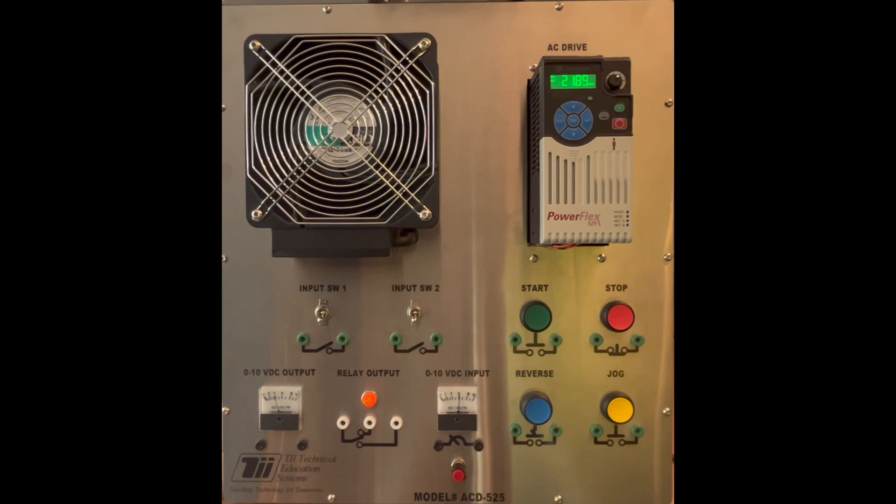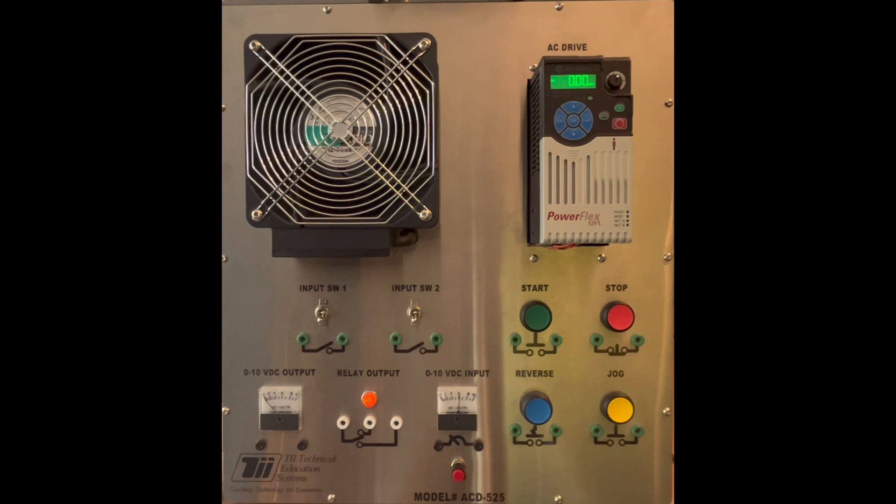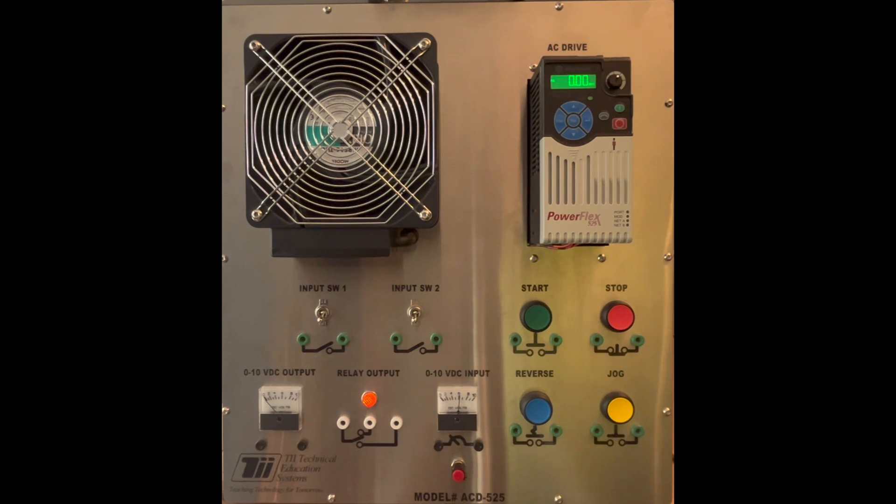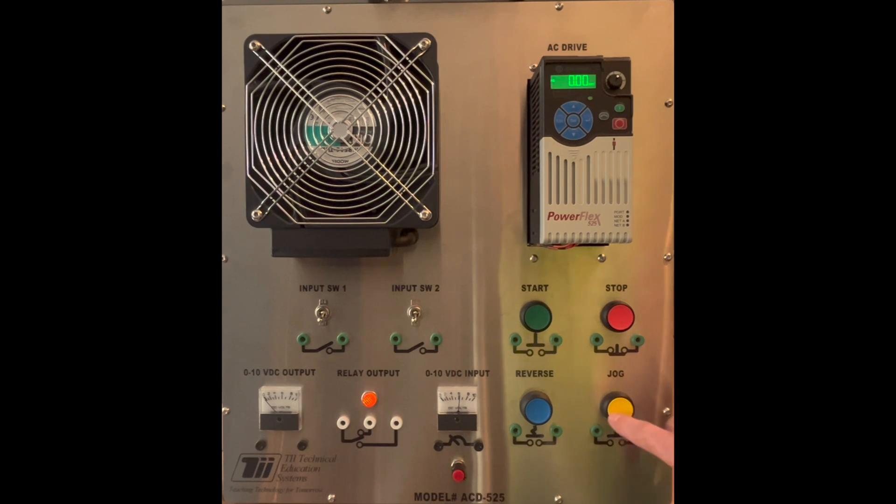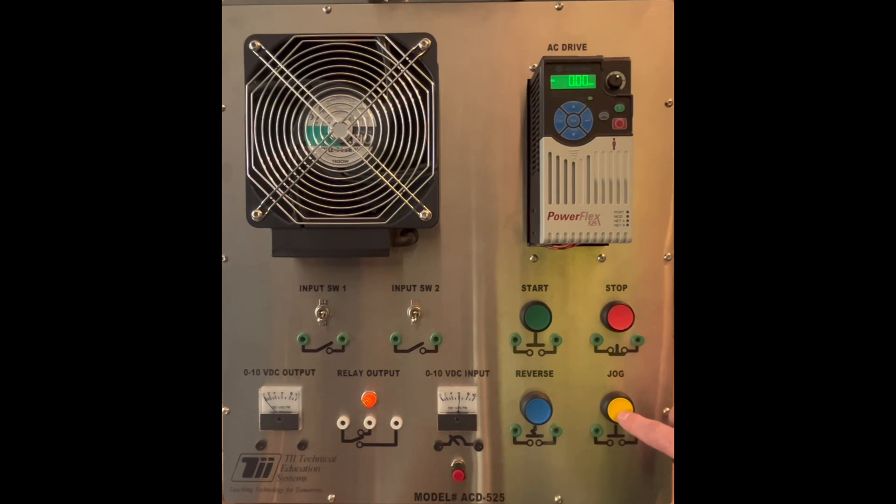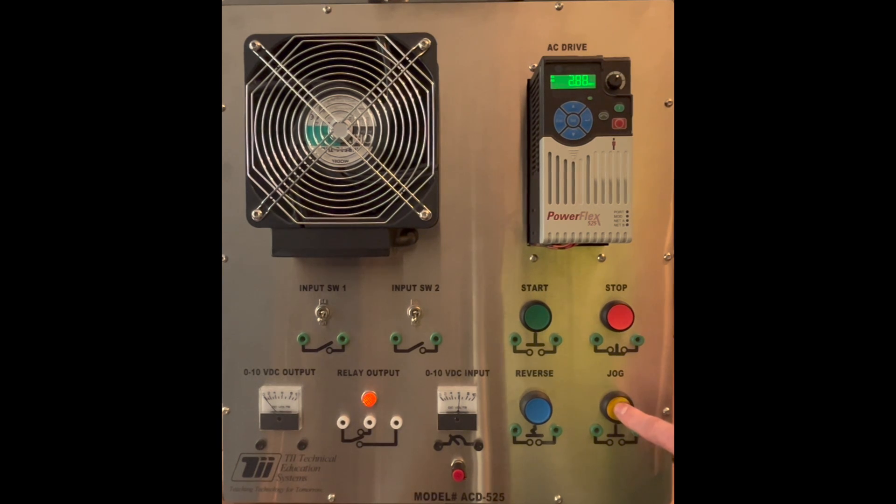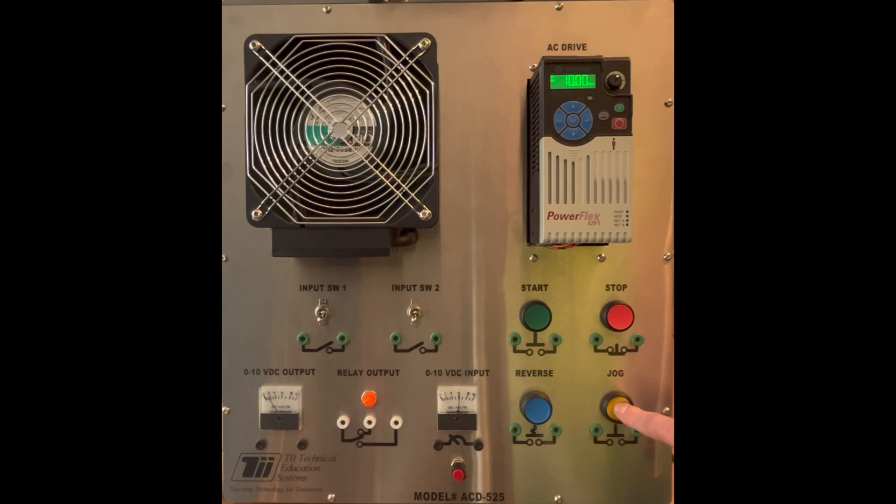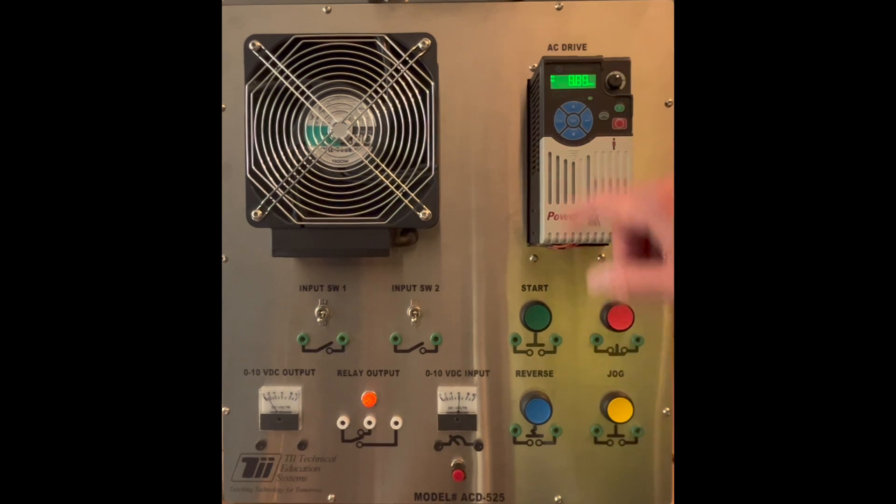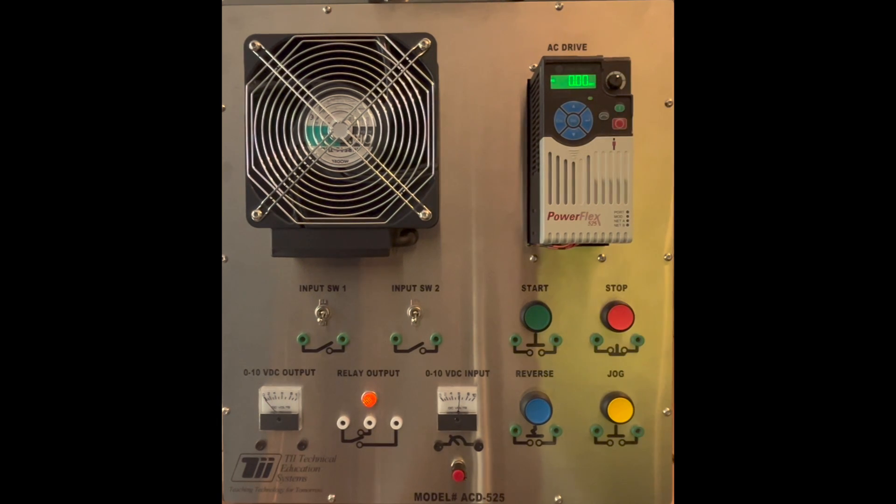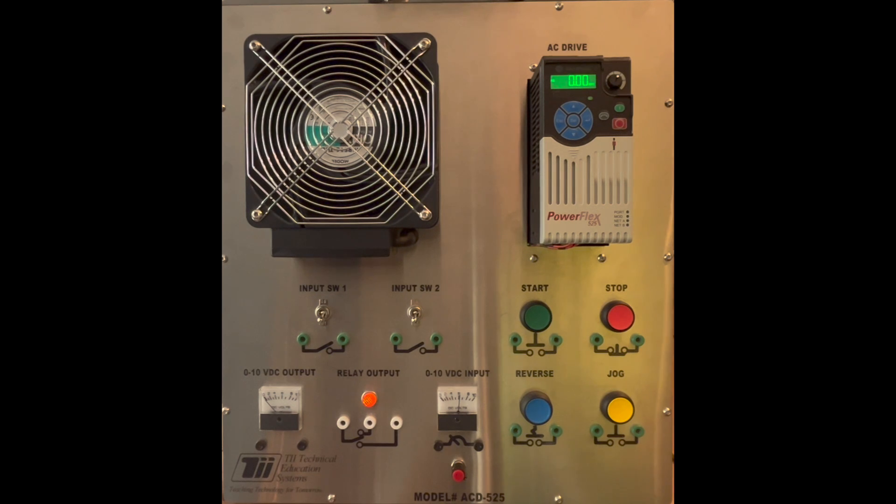But if I need to jog this forward, let's say it's on a conveyor belt and every once in a while when the e-stop activates it gets out of sequence with where it needs to be. So they add a jog button in here so the operator can activate the jog button to move the conveyor belt forward at a pretty slow pace, this case of 10 hertz, and that 10 hertz can be adjusted in the PowerFlex menu.